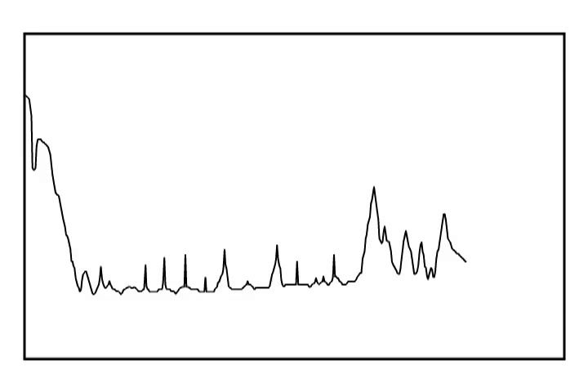Filtering. If we were to look at a raw echo profile, it would look like this. This is a horrible echo profile. All those small spikes are making it difficult to see the true material echo. In most instances, these spikes are caused by electrical interference.